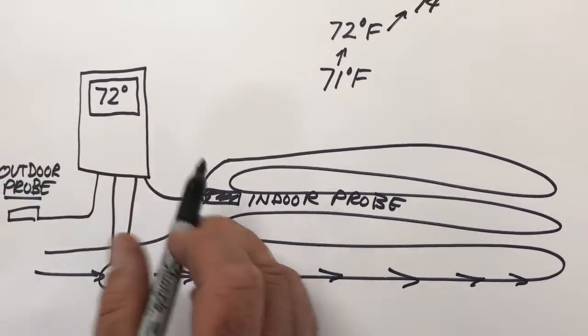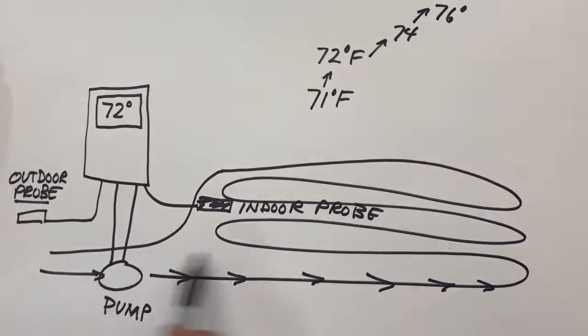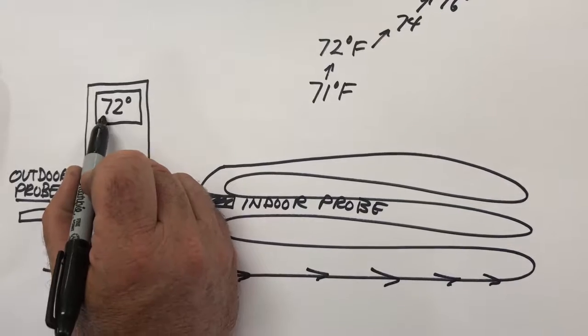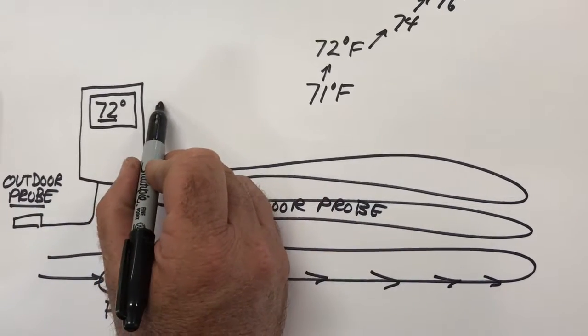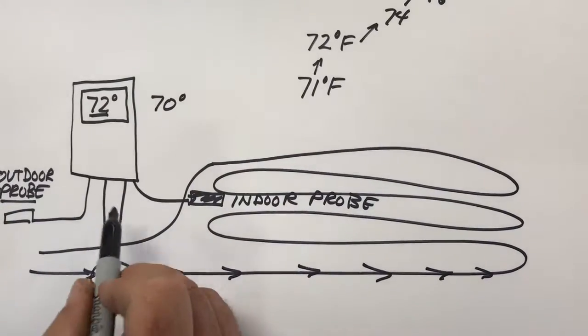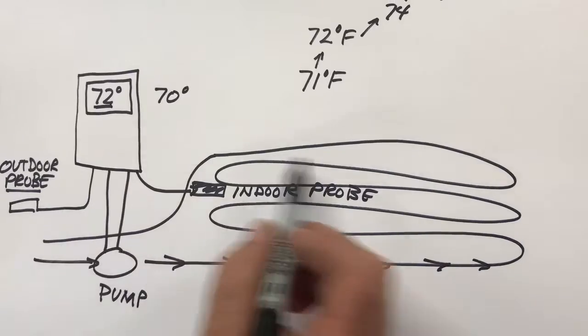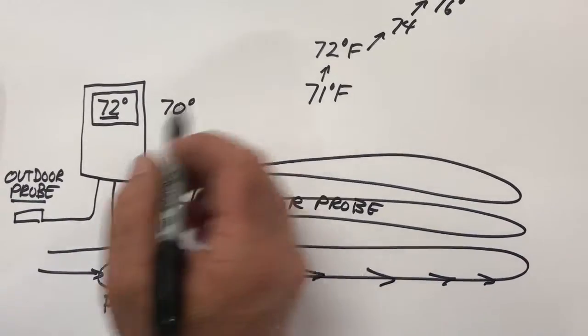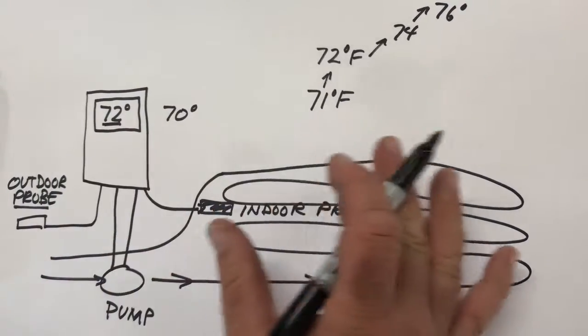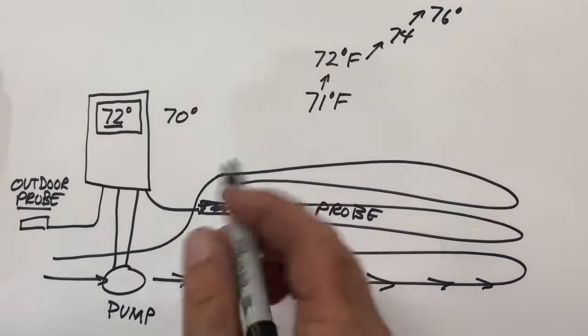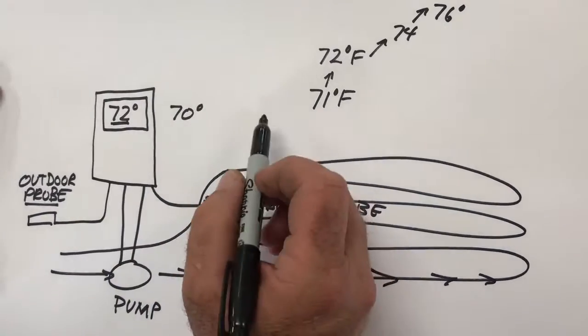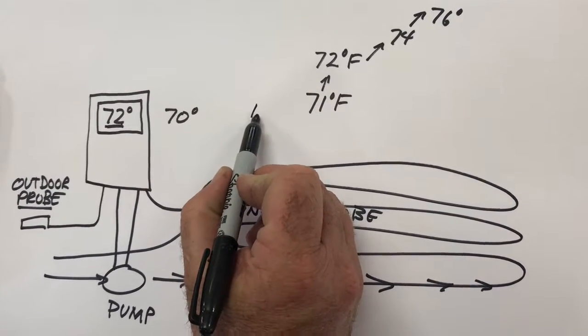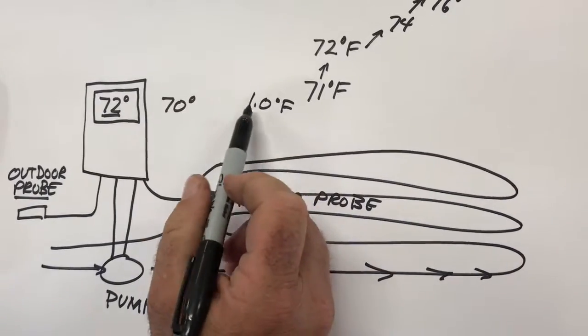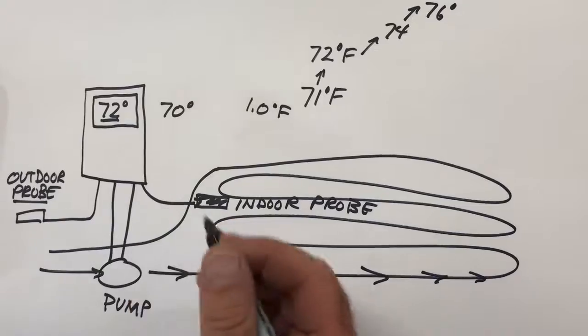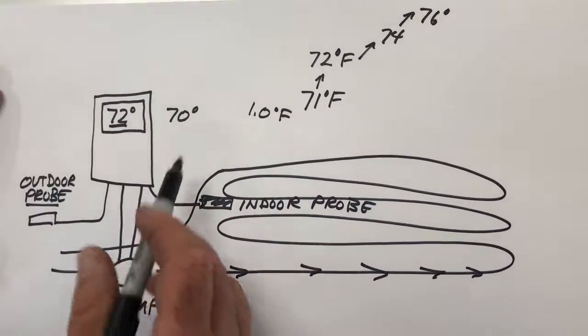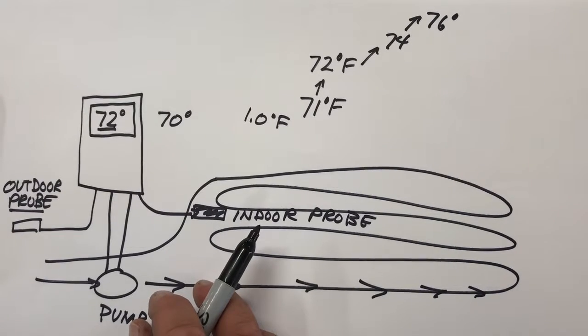It's really quite sophisticated. So for instance, after a few days of operation, your smart thermostat system might come to know that if I want a 72 degree room temperature, it's going to shut off the circulator pump at 70 degrees because it knows that at a given outdoor temperature, the system tends to overshoot the set point by 2 degrees. So in practice, what you get is a much smoother temperature performance in your room. In my experience, when I've installed these systems, they are accurate to within less than 1 degree Fahrenheit, so sometimes a half a degree. So the temperature is very, very even. The comfort level is excellent. And these smart systems aren't really any more expensive than a regular dumb thermostat.